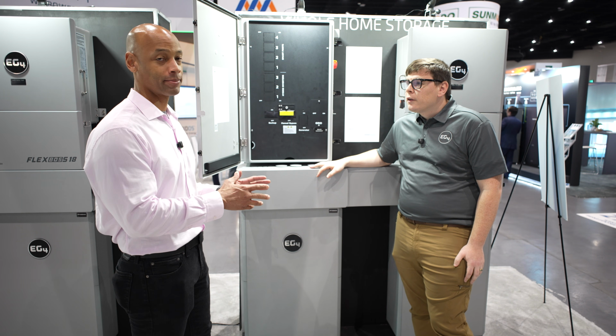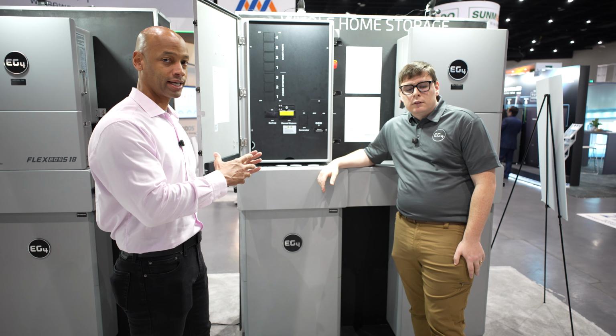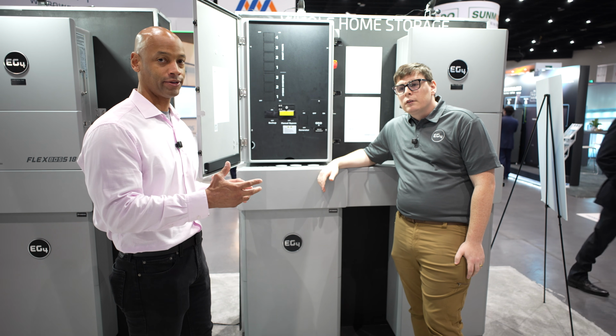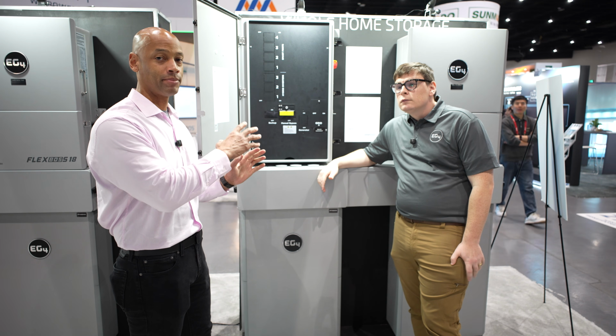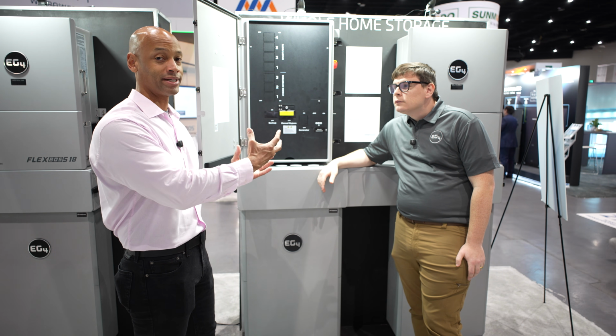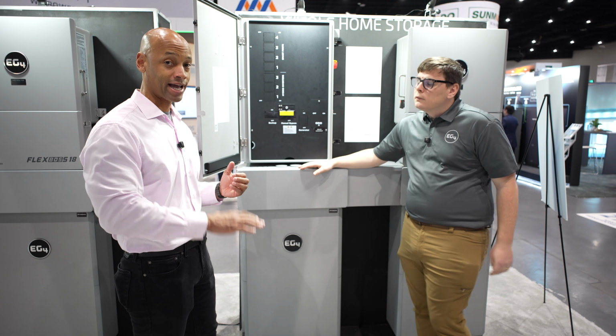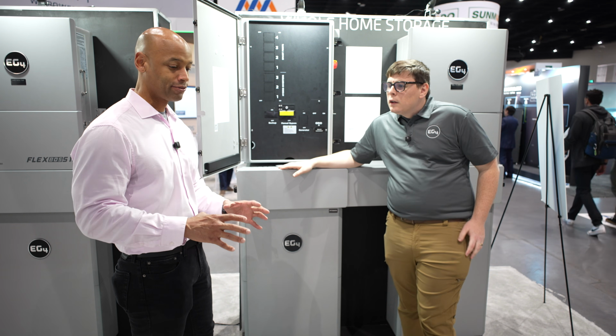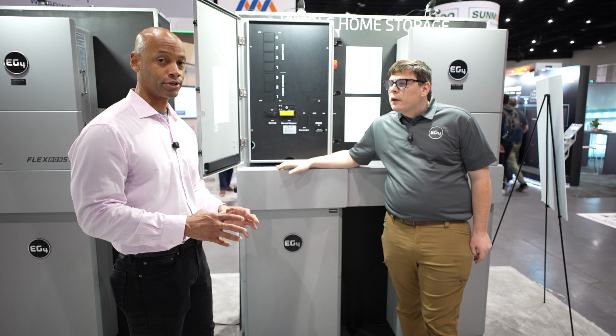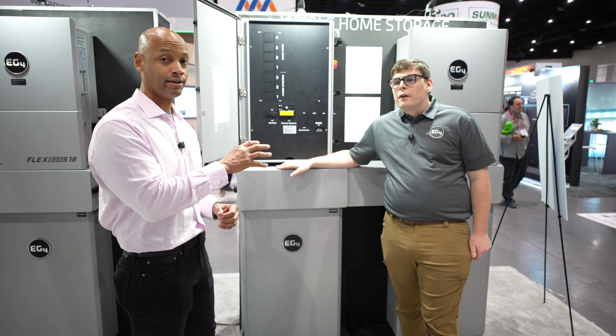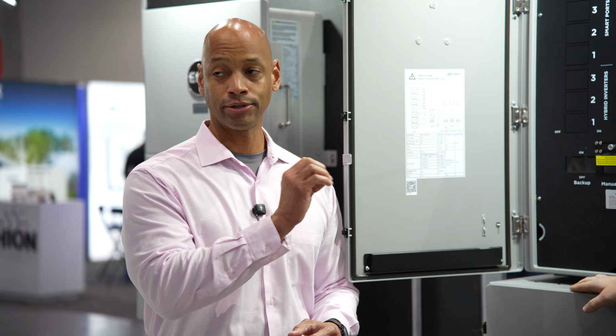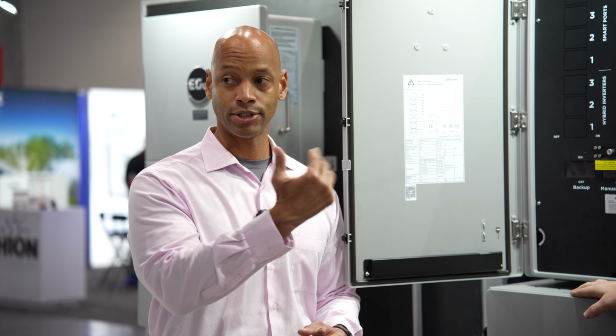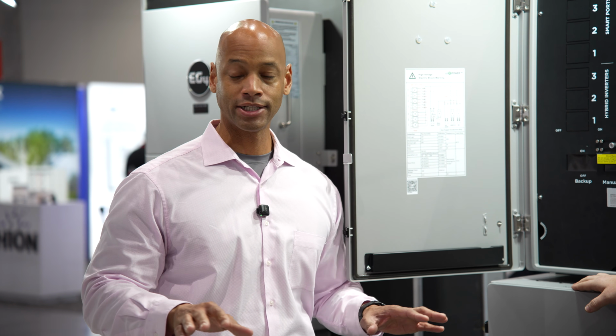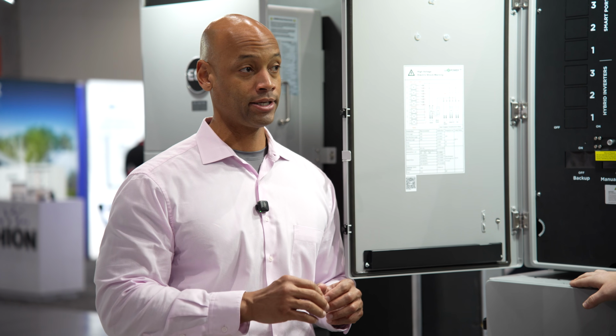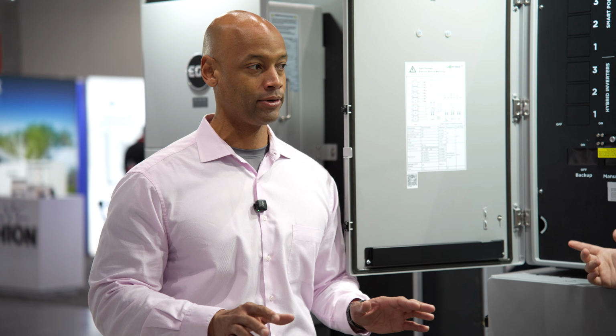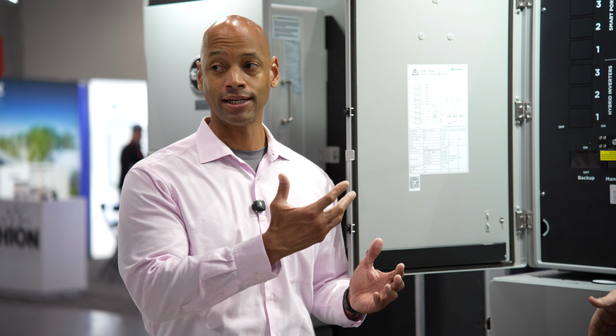So what James is talking about here is, if you're going to connect a system like this in an AC coupled configuration, meaning, let's say you've got microinverters on your solar panels, but you want to be able to take that power in to recharge your battery after your battery's been depleted, you have to hold a little bit of the battery energy in reserve just to keep the inverter on, so the inverter can send some voltage to the microinverters to wake them up to start sending power in. If everything shuts down completely, the microinverters think the grid's down, so they shut down completely too, and everything's off, where you could have sunlight you want to come in.